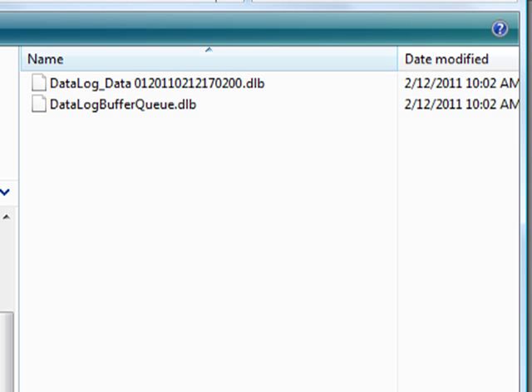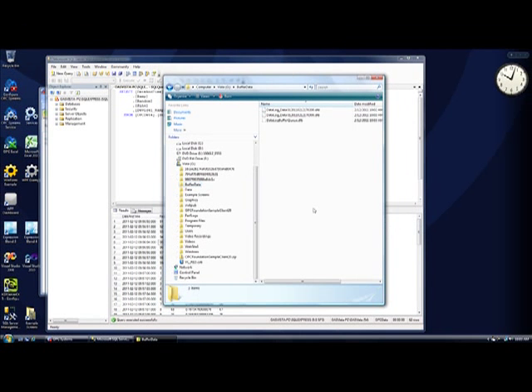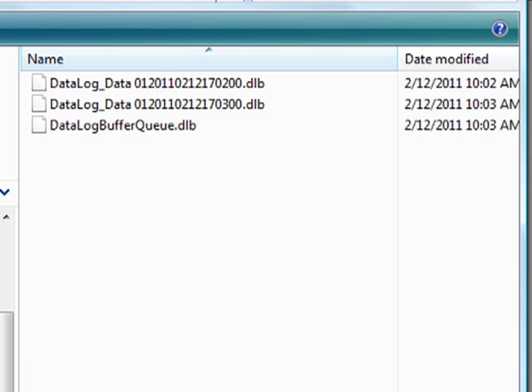This is a great solution if you have satellite connections or remote data sources that you'll only be able to connect to occasionally. Now that we have another file, let's go ahead and start the database engine back up. When the service is able to reconnect to the database engine, it will process these files in the order that they were archived and all of the values that are contained within these files will be logged into the database engine and there is no data loss during the downtime of the database engine.